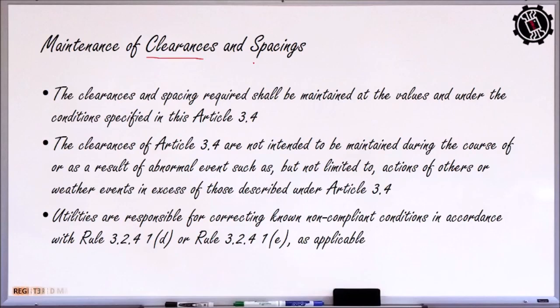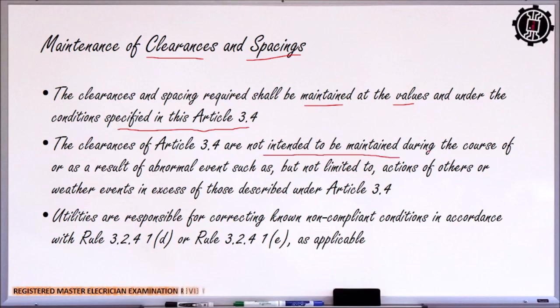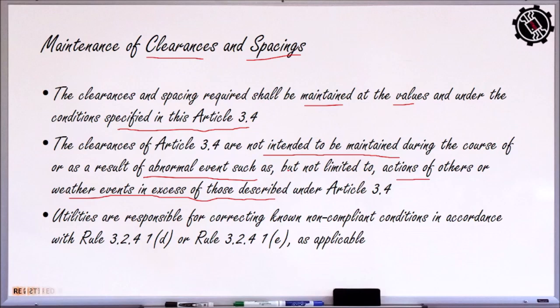So, maintenance of clearances and spacing. So, the clearance and spacing required shall be maintained at the values and under conditions specified in this article, Article 3.4. So, the clearances of Article 3.4 are not intended to be maintained during the course or as a result of abnormal event, but not limited to actions of others or weather events that exist, those described under this article. No? So, ano ibig sabihin nito? So, in normal conditions, the clearances must be always maintained. So, kung 4.8 meters sa umaga, 4.8 meters din yan sa gabi. So, that is considered as maintained natin yung ating clearance.